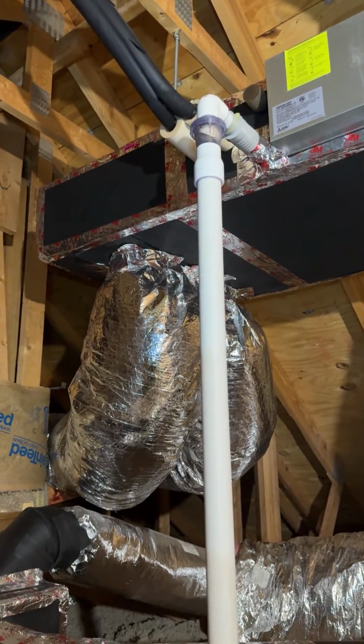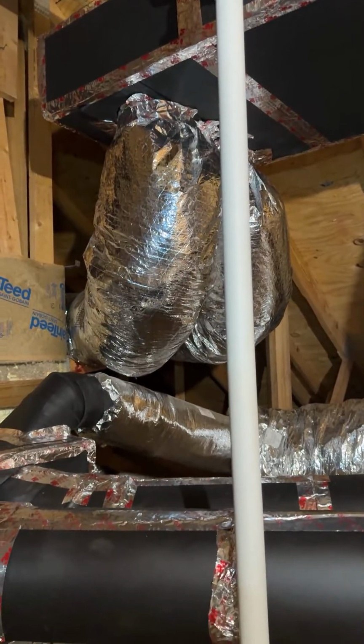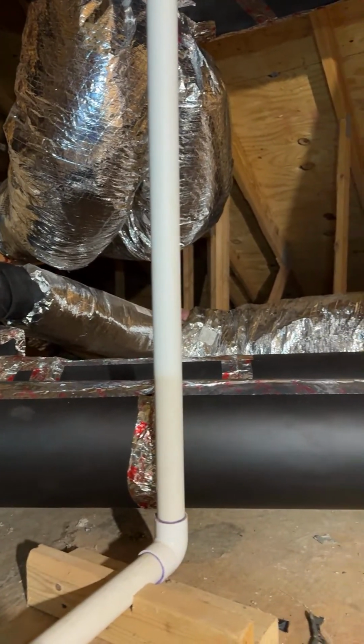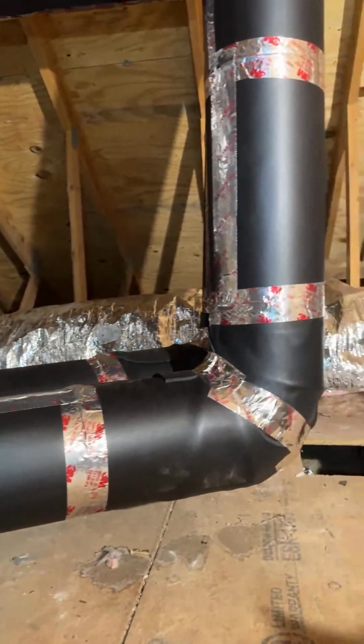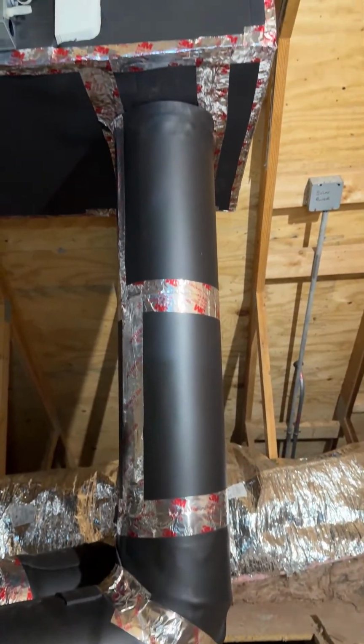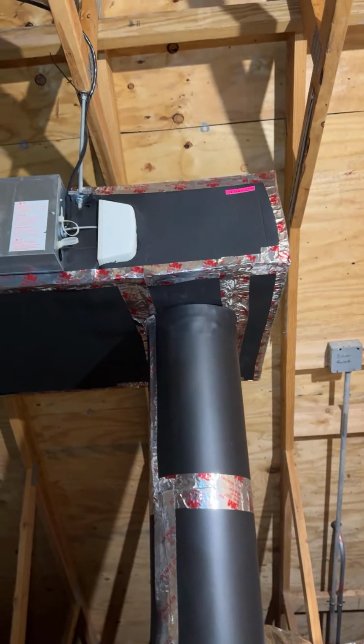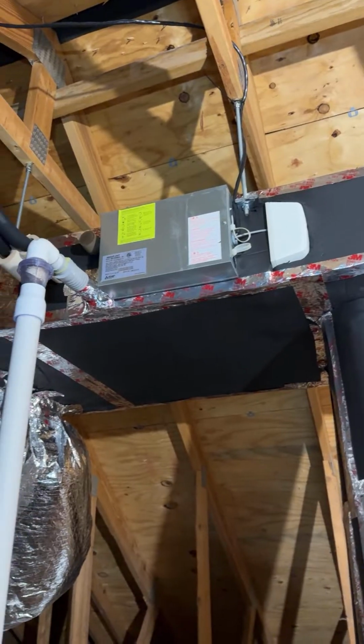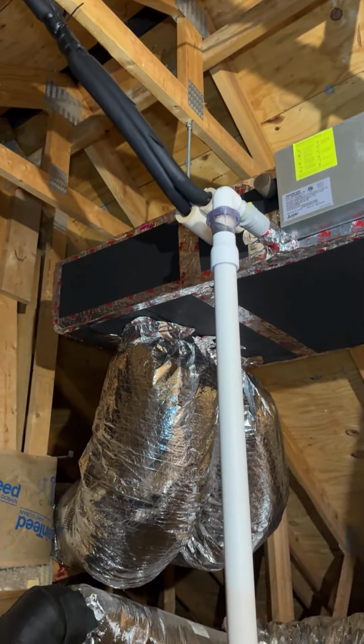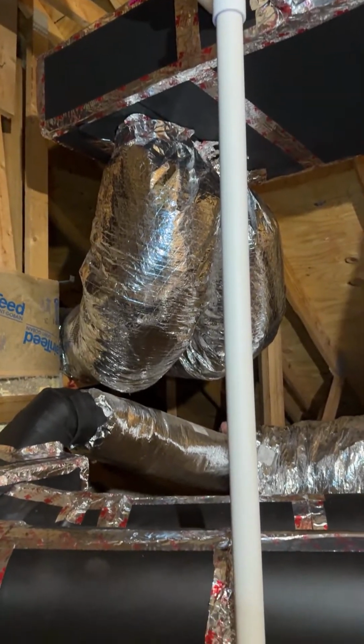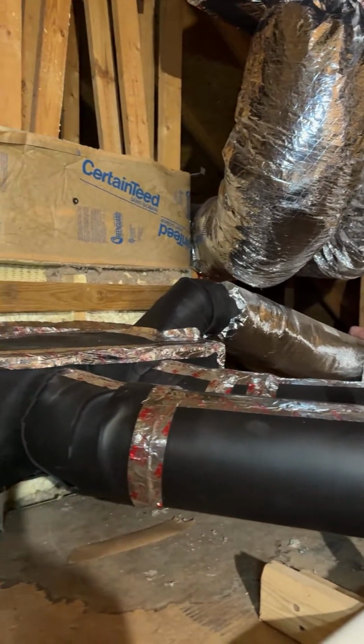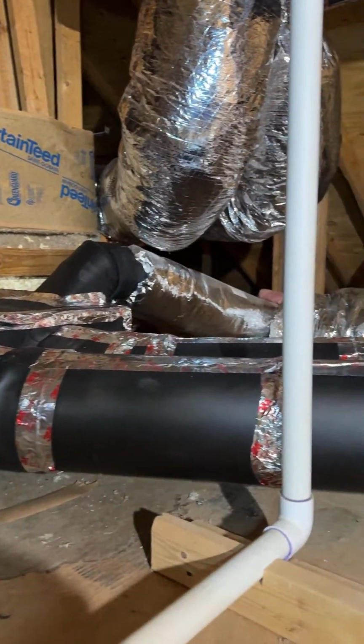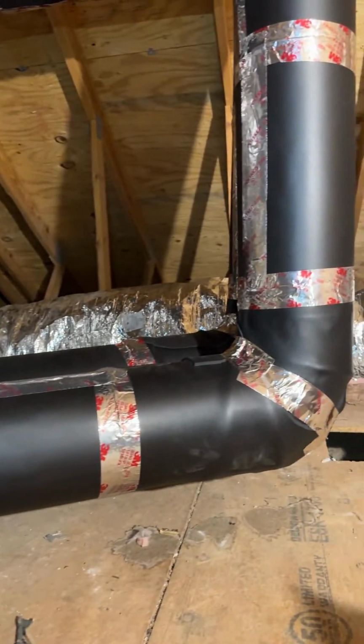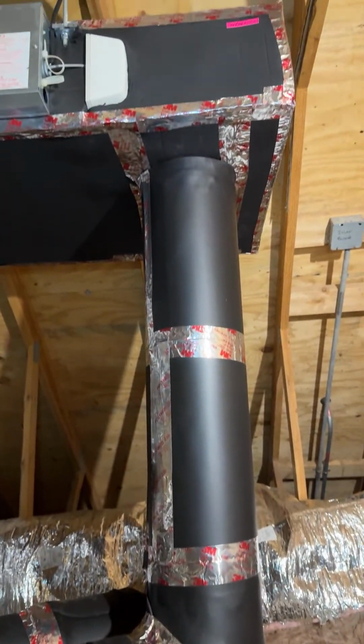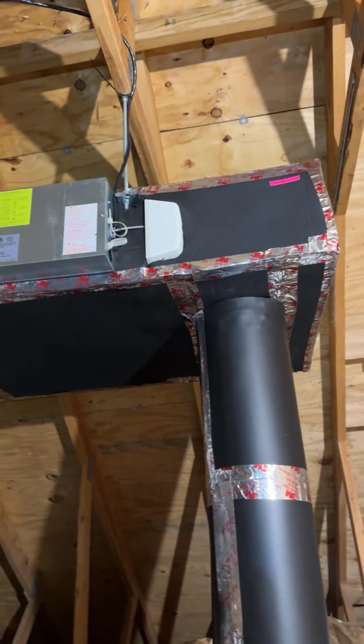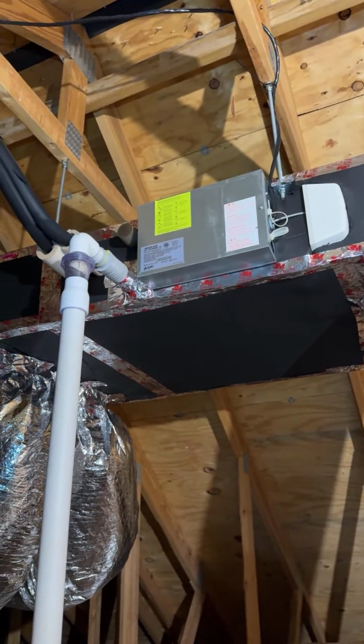And then if that wasn't enough, when we did this system and modified the ductwork about a year ago, we pulled all of the refrigerant out of the system. We weighed it to see how much we had so that we could put more in. And we realized at the time that we only had 1 pound of refrigerant. And this is a 9,000 BTU unit. The outside system is on a multi-system, so it shares an outdoor unit, which sits over 50 feet away. And if you know anything about refrigerant lines and how much refrigerant is needed, putting only 1 pound of refrigerant is not going to do it. So we weighed in and put the correct amount of refrigerant in, and it works wonders right now.